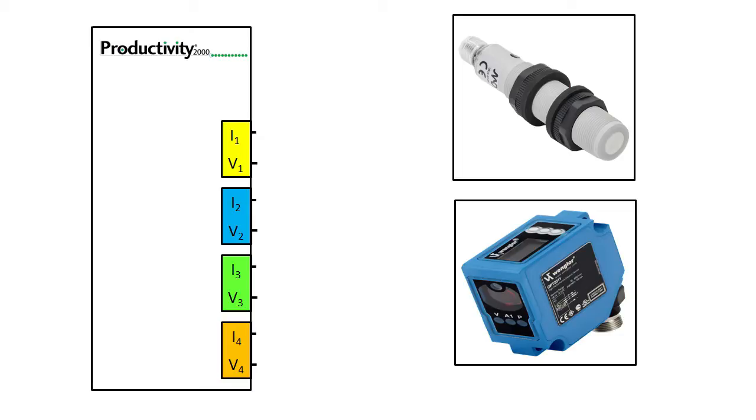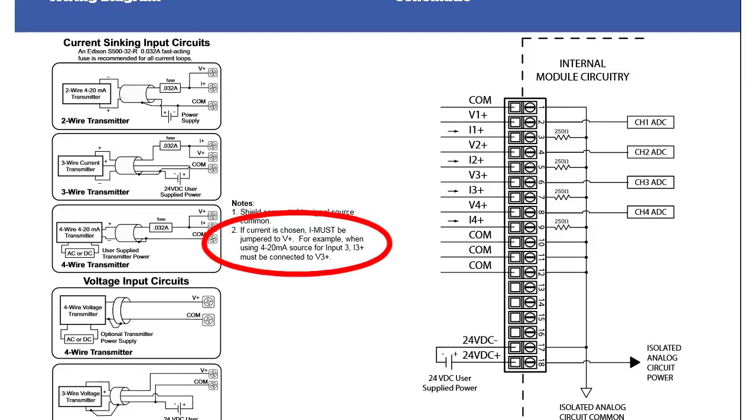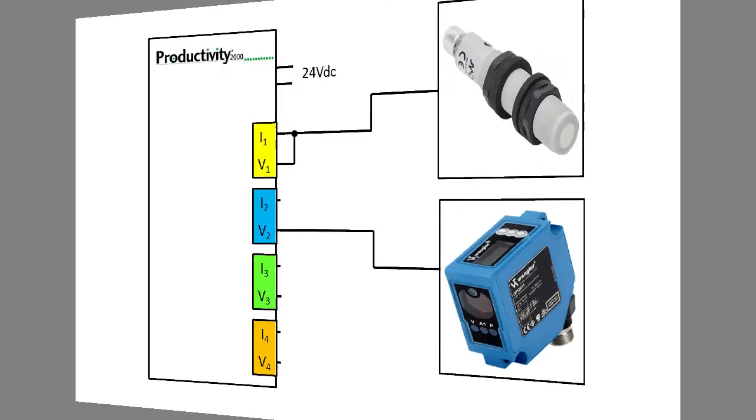That's really handy that you can do both voltage and current on the same module. Let's wire the ultrasonic sensor's current output into channel 1 and the laser sensor's voltage output into channel 2. Make sure you add this jumper to any current inputs – there's a little note here in the datasheet to remind you but it's easy to miss. This module also needs 24 volts.